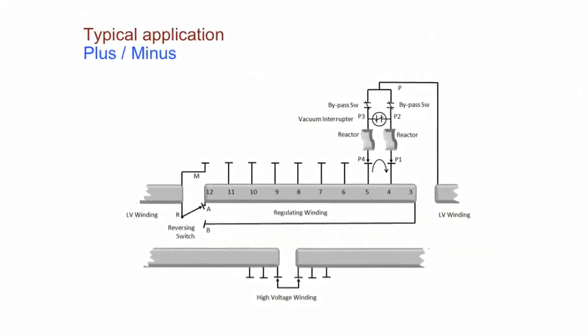This is what we're talking about when we have a plus-minus tap changer. Basically, you have your leads coming out from your transformer winding, what we call the regulating winding. Your reversing switch basically just gives you your additional taps when it taps up or taps back down. It gives you 2, plus and minus, is what it ends up doing. It adds turns in, takes turns out. The tap changer then just steps from one point, and then this one would step over. So it'll just move along step to step.